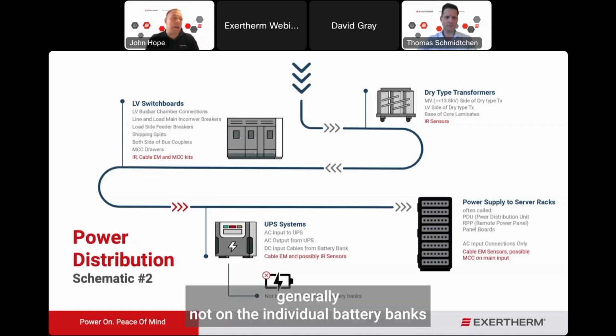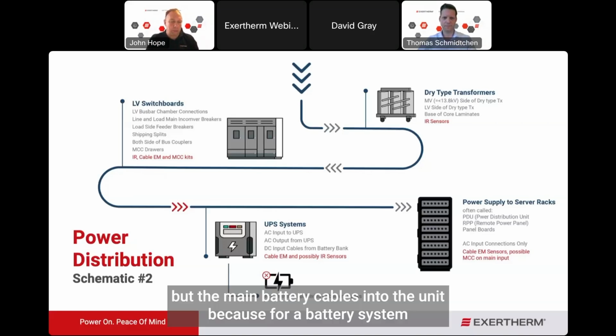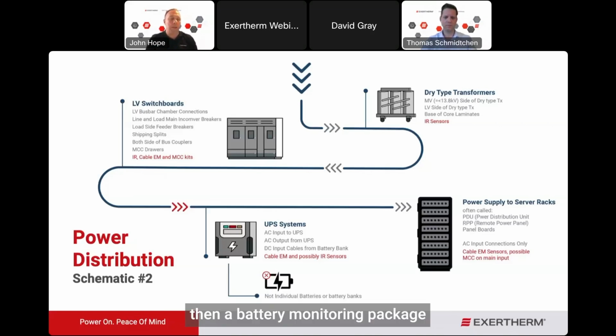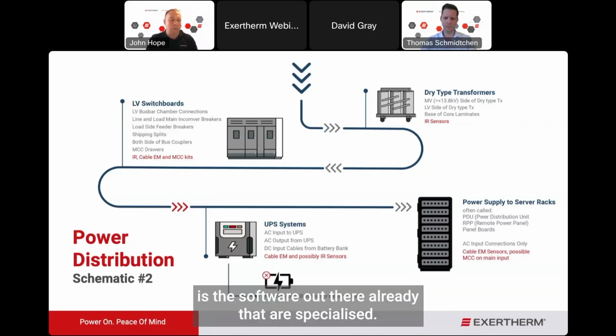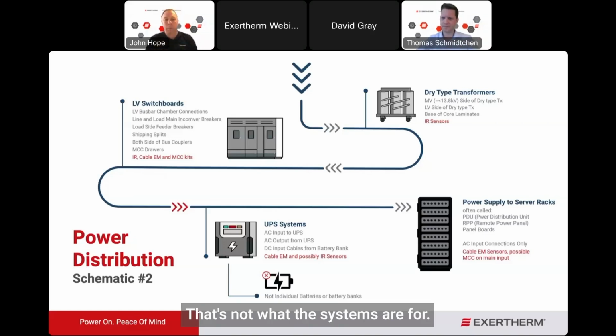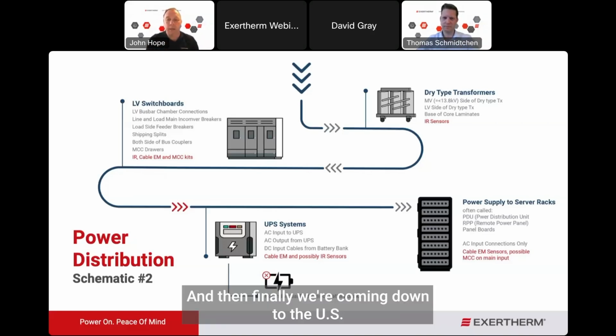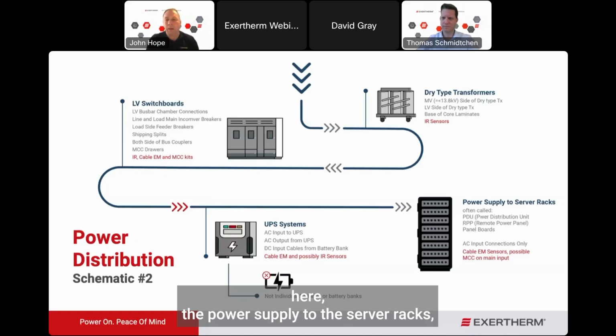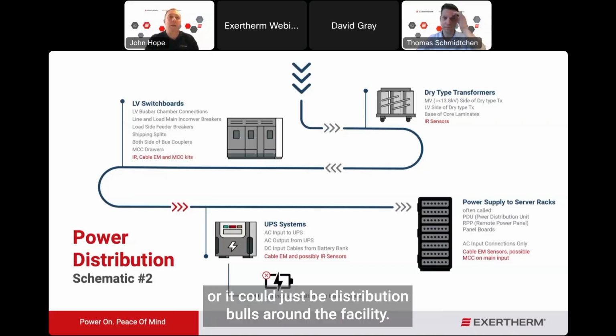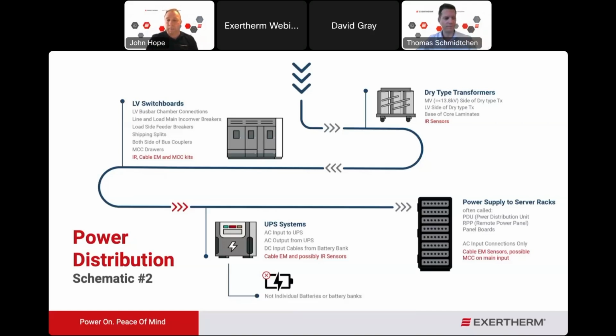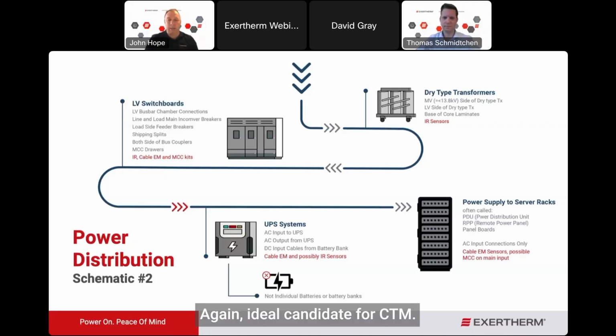Generally not on the individual battery banks, but the main battery cables into the unit, because for a battery system, there are battery monitoring packages and software out there already that are specialised. That's not what the CTM's there for. And then finally, we're coming down to the power supply to the server racks, or it could just be distribution boards around the facility. Again, ideal candidate for CTM.